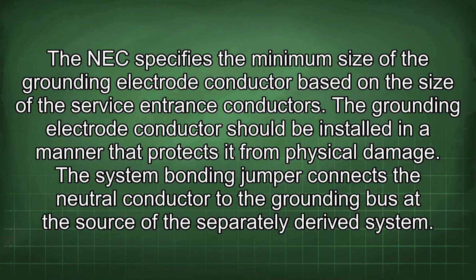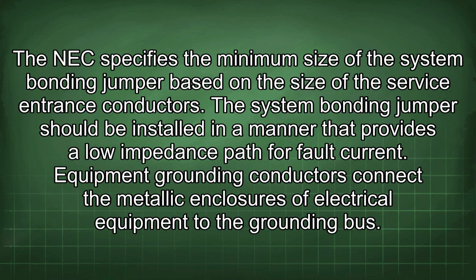The system bonding jumper connects the neutral conductor to the grounding bus at the source of the separately derived system. The NEC specifies the minimum size of the system bonding jumper based on the size of the service entrance conductors. The system bonding jumper should be installed in a manner that provides a low impedance path for fault current.